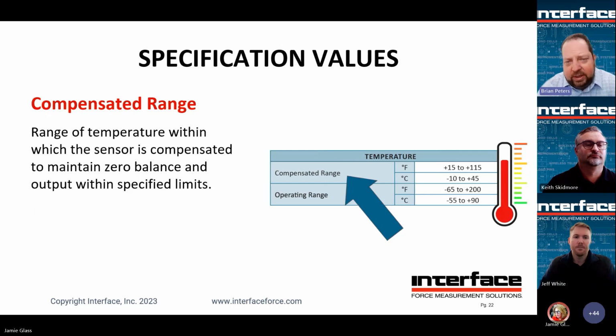So compensated range is the temperature range within which we guarantee the sensor to maintain its temperature-related performance specs. So you'll see in this example, in the table there, operating range, -65 to 200, and we have a compensated range of 15 to 115. The other thing to note too is that most Interface products have a cold to hot compensated range. Competitors often will do room to hot. But the cold to hot is definitely flatter. And again, within that compensated range, it's going to maintain certain specifications. So on the next slide.